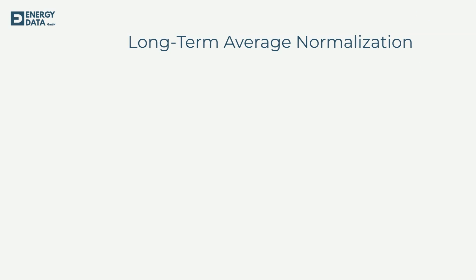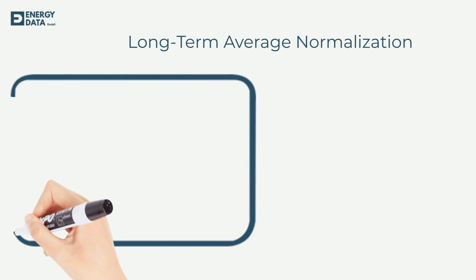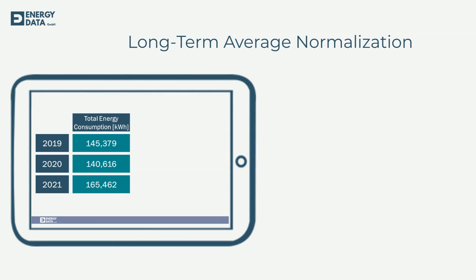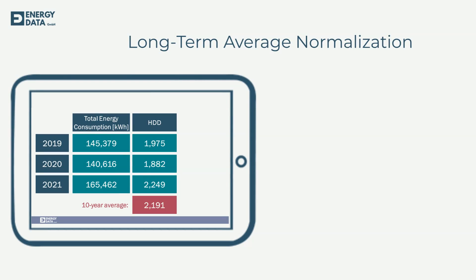The common approach is normalization by using the long-term average. We go back to our example but now we add another variable: the 10-year average of heating degree days. Of course, location, base temperature, and length of the period should be the same. Our free degree day calculator will calculate the long-term average with just one click.